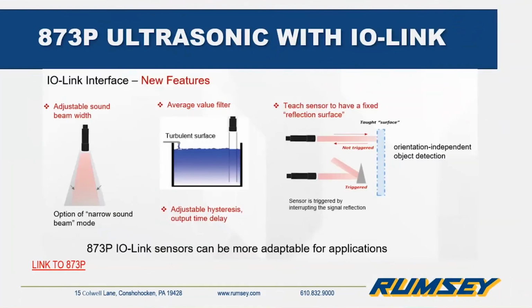Next slide, please. So if you're using IO-Link, some of the tough things for an ultrasonic sensor is when you're using a narrow vessel. That sound beam will hit the walls of the vessel the further away you go from the sensor. So with IO-Link, you can adjust that sound beam. We used to use a cardboard cone to narrow the beam and kind of play with the sensitivity to filter out the cone, but IO-Link will narrow that beam for you.